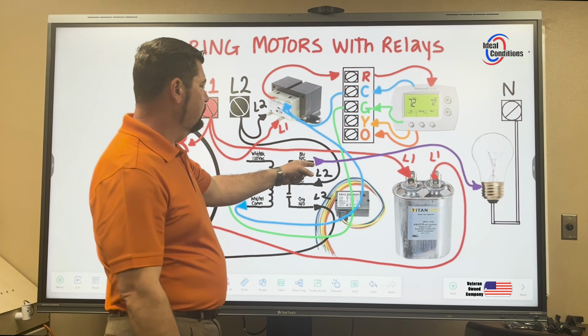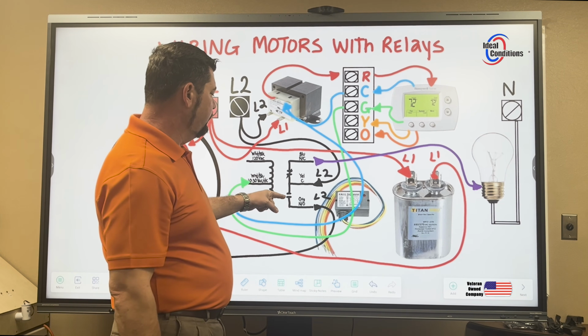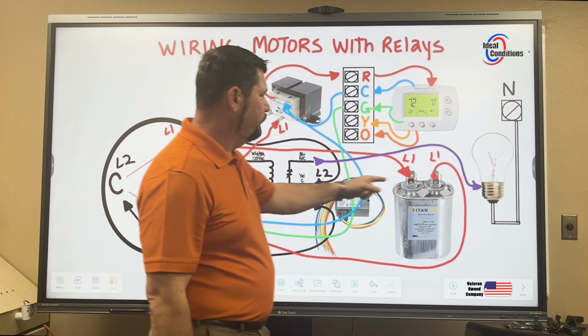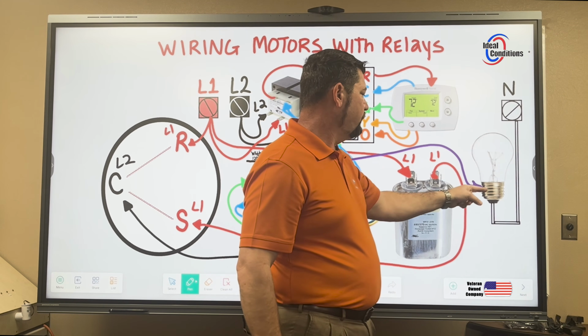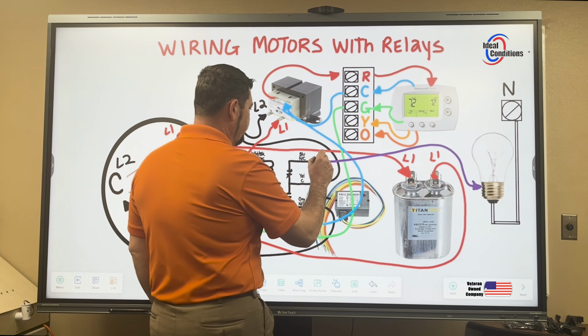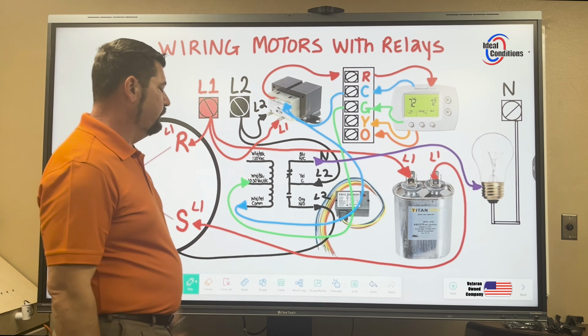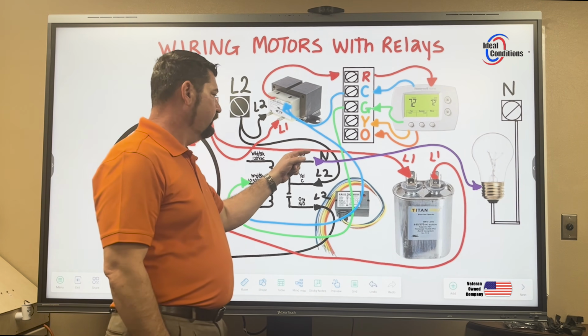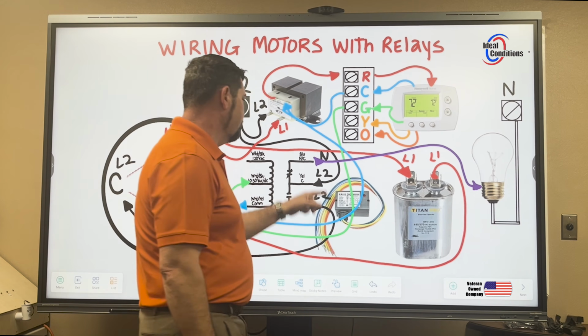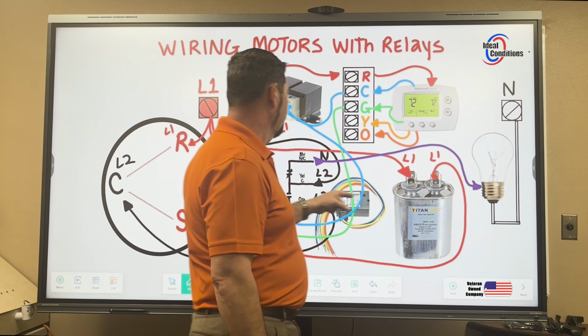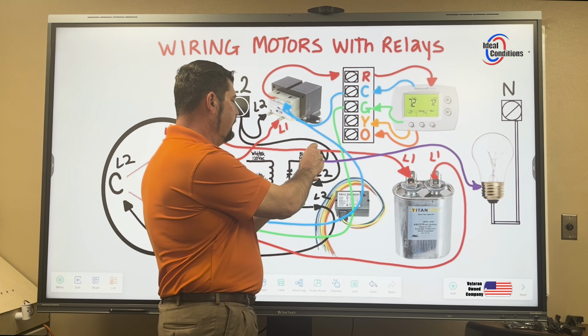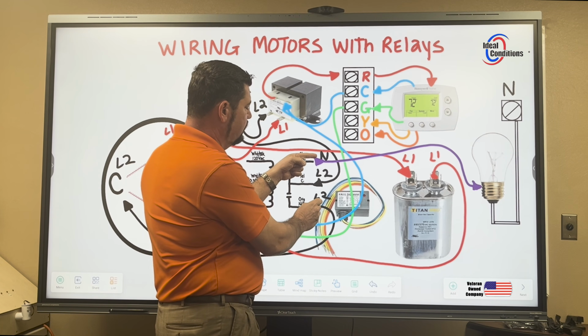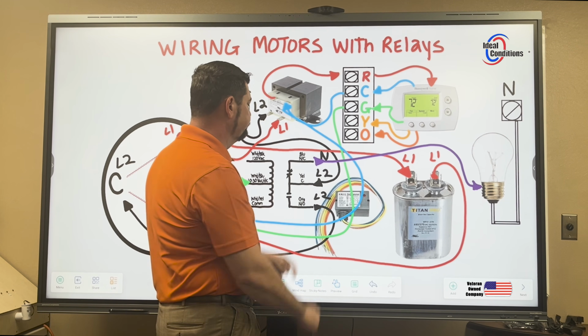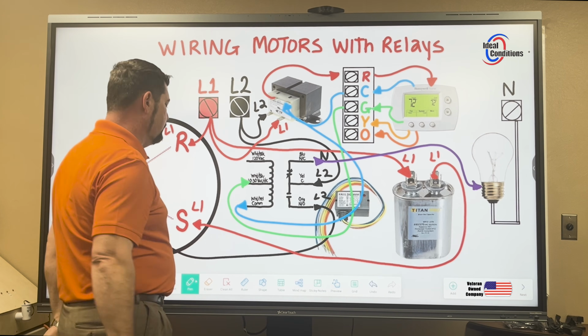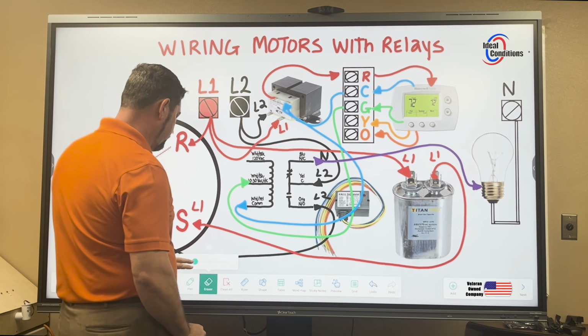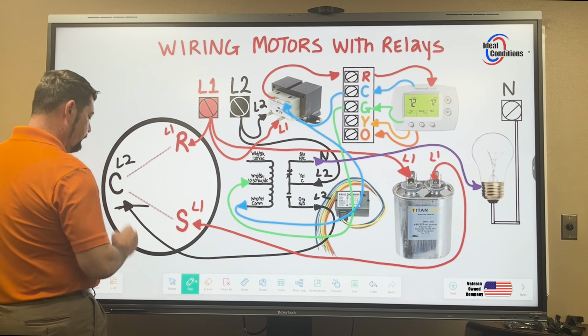But what will I have here? Well, the moment this opens and this closes, then what will happen here is neutral has a path all the way through the filament in the bulb, all the way back to here. So theoretically, I'm going to have neutral here at this present time. Until there's L2 present, then neutral will be back over here. But when L2 is not present here, neutral's path will be here. So I would measure 120 between here and 120 between here. Between here and here, I would read 0. Between here and here, I would obviously read 24 volts. Let's see if we can do this another way. I'm going to go ahead and erase all this.